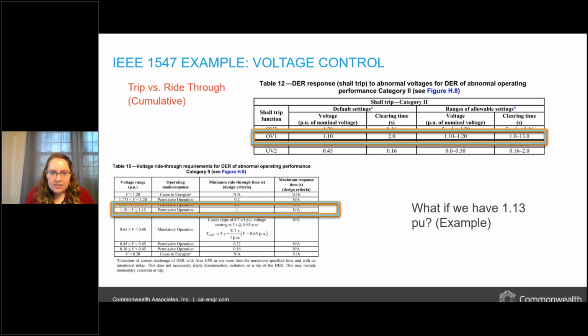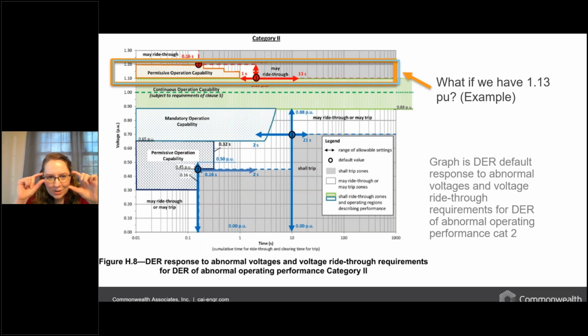So there's another way we can look at this in a graphical representation. And if we look at our slice of where approximately 1.13 per unit is on this graph, at a minimum, we can recognize there's 3 colors on the graph. So this represents our options of permissive operation, ride through, or tripping throughout various timelines. So from this, we see there's really no correct answer to our poll question. So we're all winners today. Instead, the correctness of the answer depends on the reliability needs of our distribution system as determined by operators.